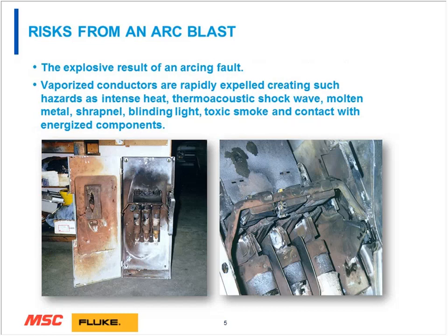After the arc flash occurs, which is that bright light, unfortunately it becomes that arc blast, and this is where the real danger does exist. This is the explosive result of an arcing fault. This is where metal is vaporized, and at 740 miles per hour, it's forced away from the surface of the panel, and all of this liquefied metal is pushed towards you. If you're not wearing the appropriate PPE for the environment, unfortunately, that's where a lot of dangers do come from. As well as blinding light, the noise is horrendous. A lot of people have experienced ruptured eardrums, and all of this happens in the blink of an eye, actually faster than a blink of an eye.